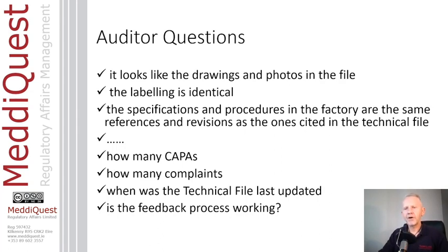So if you followed an unusual structure for your device, show a cross-reference to 13485, show a cross-reference to the Medical Device Regulation. Be prepared to prove to them that your technical file is right, but don't compromise on the fact the technical file isn't written for some box-ticking bureaucrat. It's written to help the investigator if something goes wrong and you've suddenly found yourself in the dock.